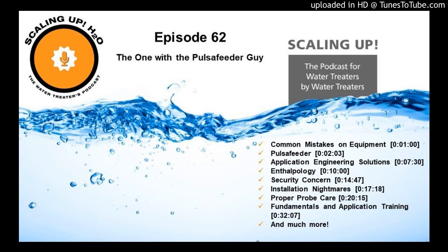So pH ORP probes should be vertically mounted, and flow should be going horizontally across them, so it's going into a T. The probe should be upright, going down into solution. And then you just observe the flow recommendations. I would strongly advise also putting a trap on the probe. And by trap, I just mean a little dip in the piping or an elbow.